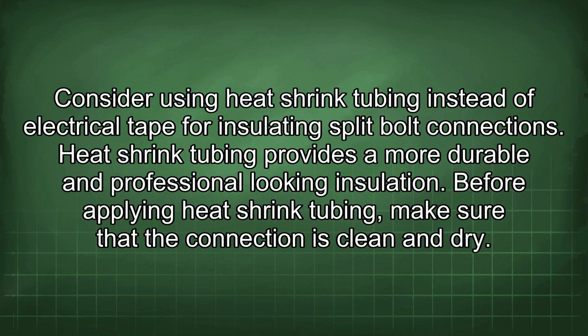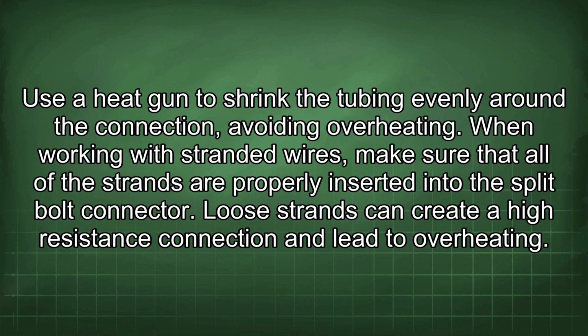Consider using heat shrink tubing instead of electrical tape for insulating split bolt connections. Heat shrink tubing provides a more durable and professional-looking insulation. Before applying heat shrink tubing, make sure that the connection is clean and dry. Use a heat gun to shrink the tubing evenly around the connection, avoiding overheating.